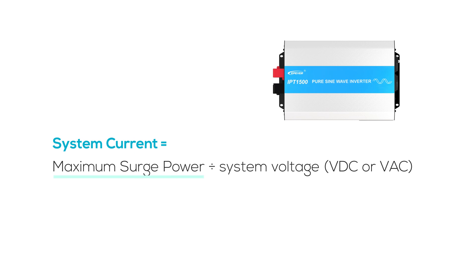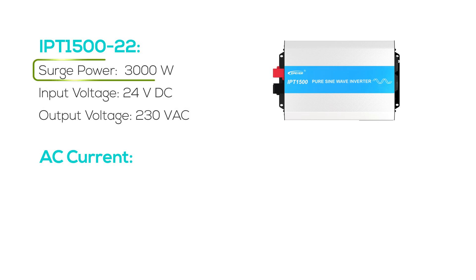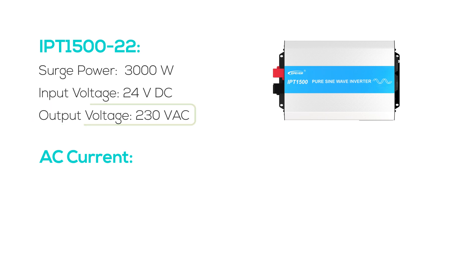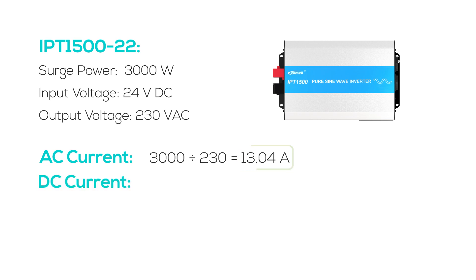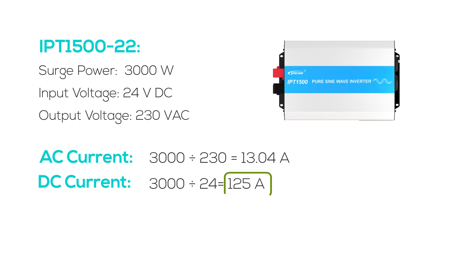Second method — when load details are not clear — take the maximum surge power of your inverter and divide it by the system voltage. Be sure to use the inverter's peak or surge power, not the continuous rating. For the AC current calculation: given a surge power of 3000 watts and AC voltage of 230 volts, the AC surge current is 13.04 amps. For the DC current during the surge, with surge power at 3000 watts and system voltage at 24 volts, the DC surge current works out to 125 amps.